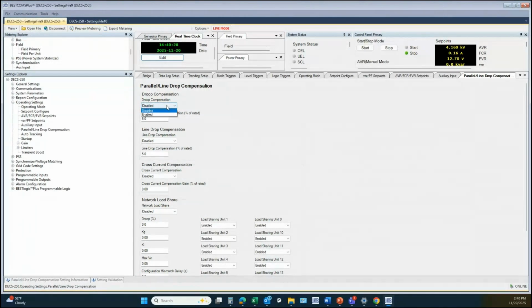Parallel line drop. This is where you would enable droop. Typically 3%, maybe as much as 5%. Some applications go beyond that. But droop is one of the more common ways to parallel generators.